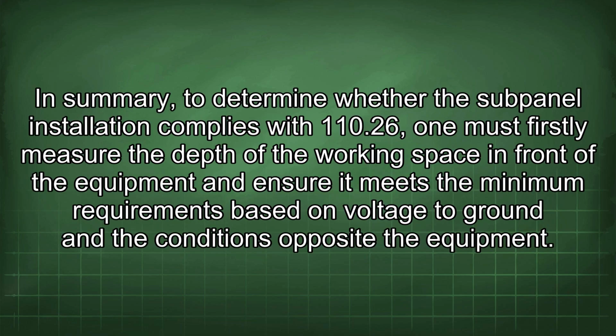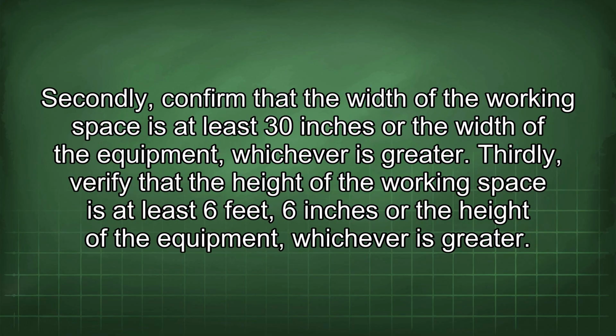In summary, to determine whether the subpanel installation complies with 110.26, one must firstly measure the depth of the working space in front of the equipment and ensure it meets the minimum requirements based on voltage to ground and the conditions opposite the equipment. Secondly, confirm that the width of the working space is at least 30 inches or the width of the equipment, whichever is greater.